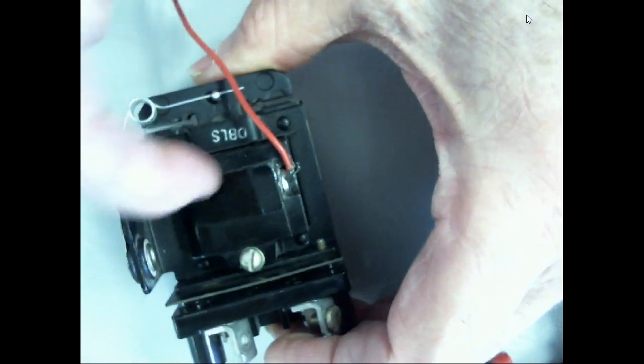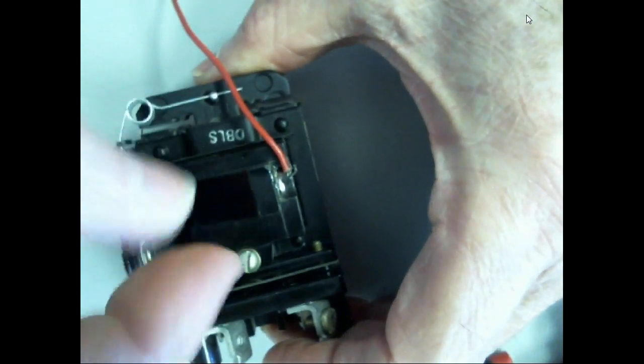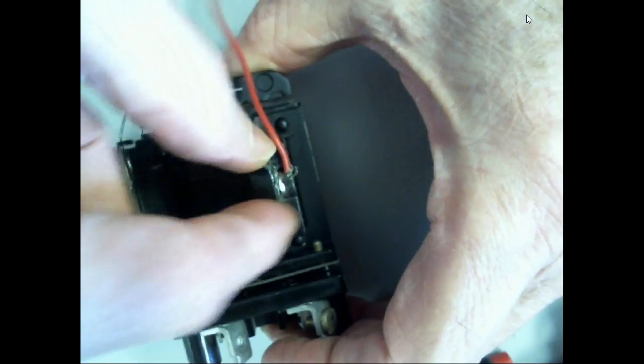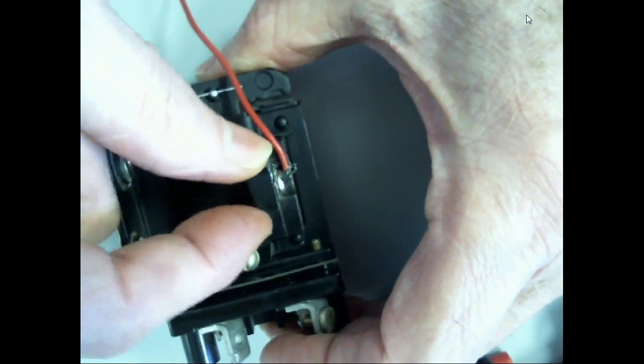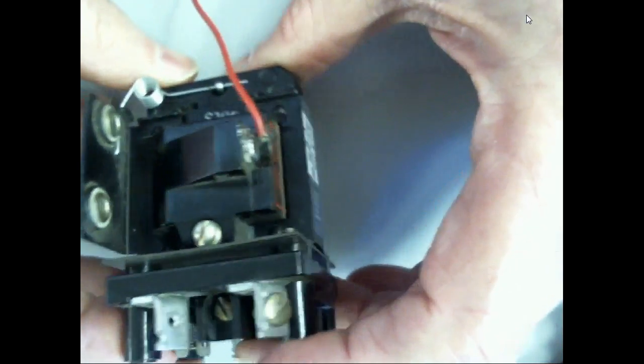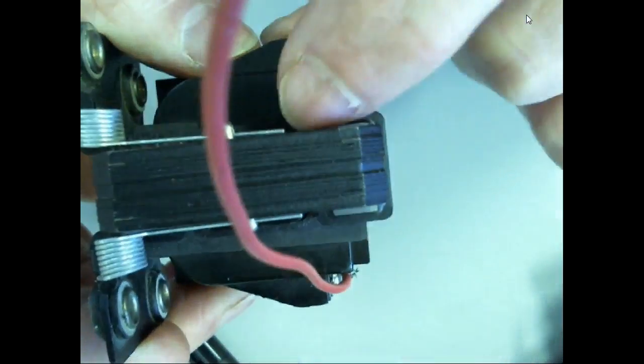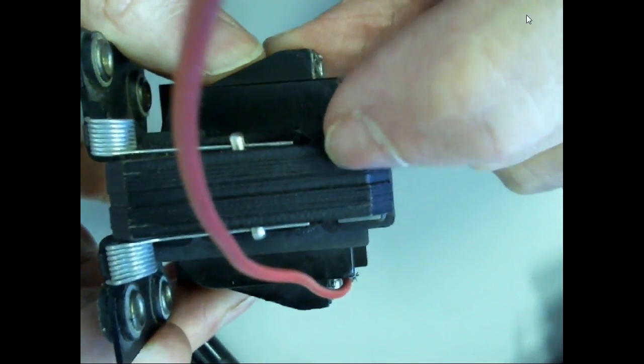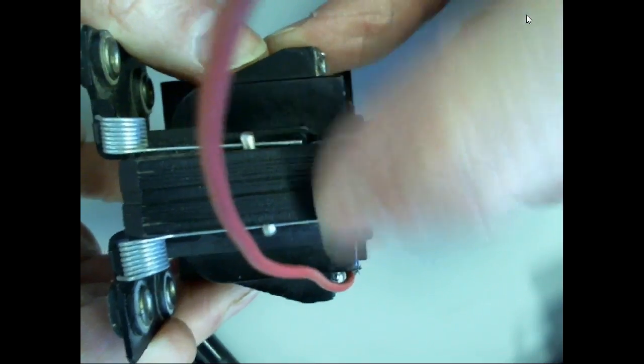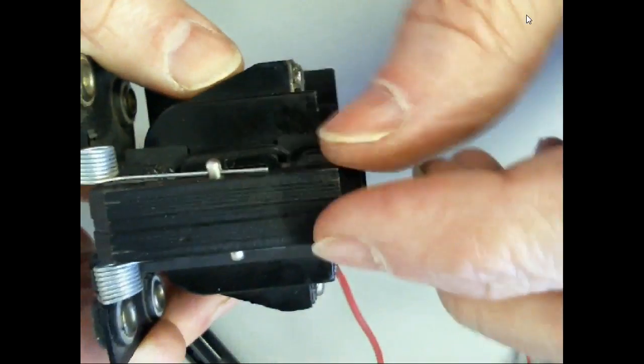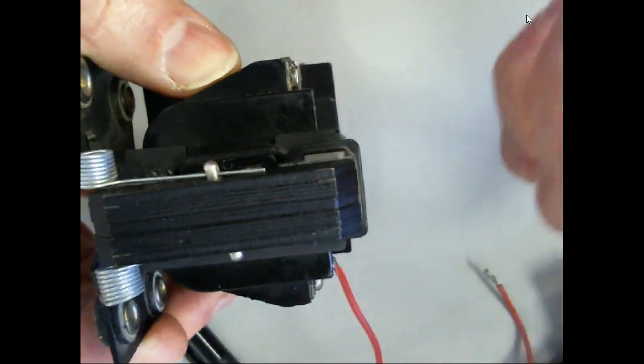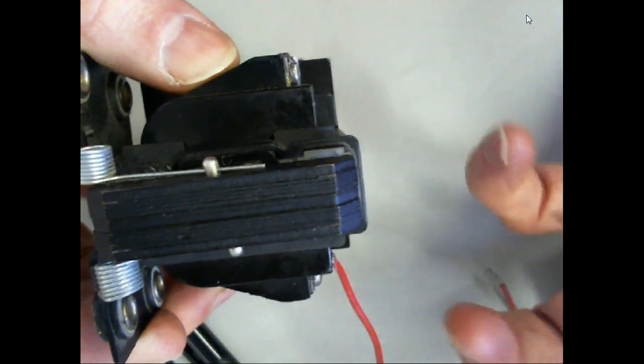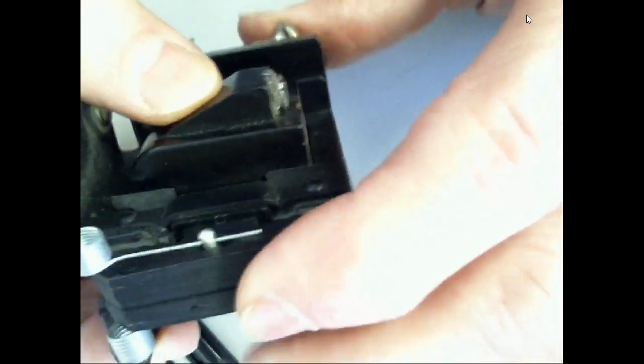So on these, the electromagnet is actually encapsulated in plastic. We can still replace this by taking the relay apart. But here's the armature - I'm going to pass this around so you can see the laminated plates, see how they're split up? So anything running off AC that needs to concentrate a magnetic field with metal is going to use these laminated plates.